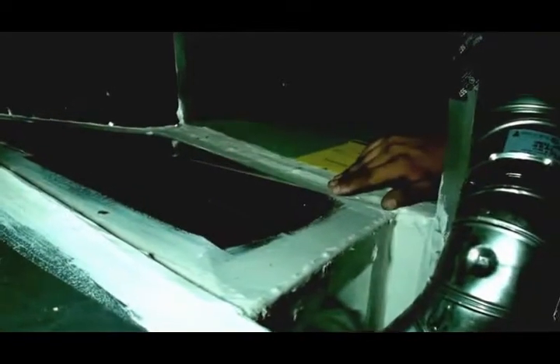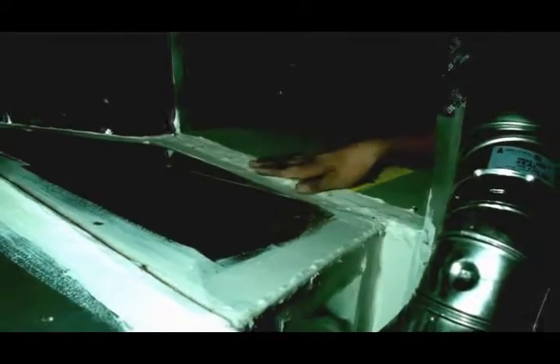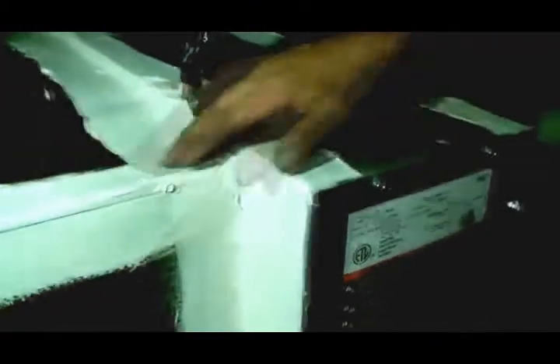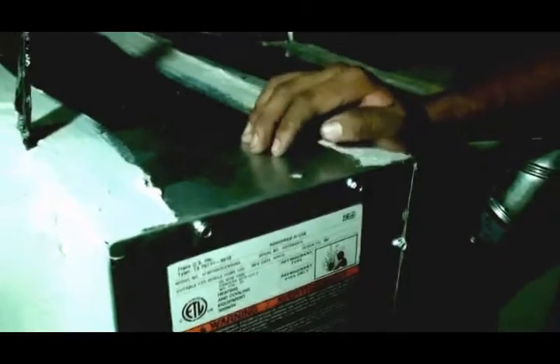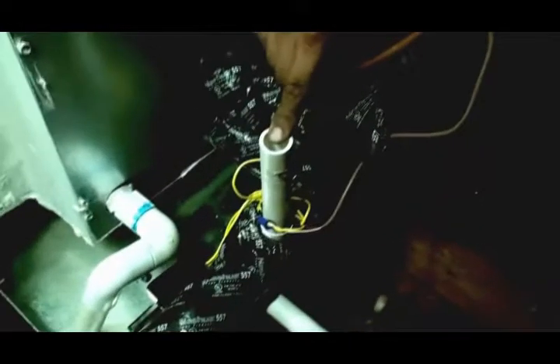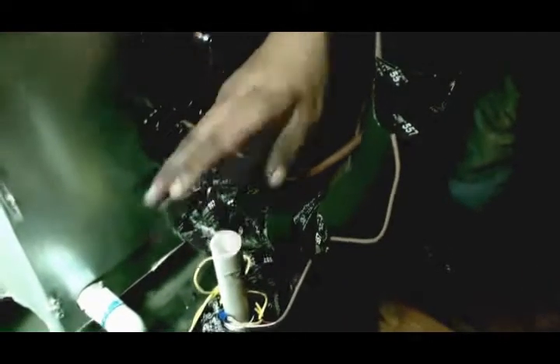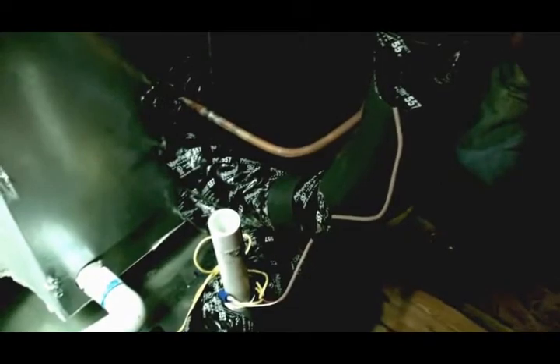Every system, every splice that we make within the system, the metal plenums, the coils, we screw them down, secure them, tape them with the silver tape that is kind of like a vapor barrier tape with mastic sealer, and we just seal every crack that we can as possible, and just make the system more airtight than what it usually is. The coil, as you see in the last one, again had ductwork plenums. We'll put the metal plenum for the supply. Upgraded the coil to a Trane coil. We've got new drain pan installed. We've got a new clean out installed for the main drain, which is blown out and made sure that it's flowing properly before we turn on the system for no overflow on the water.